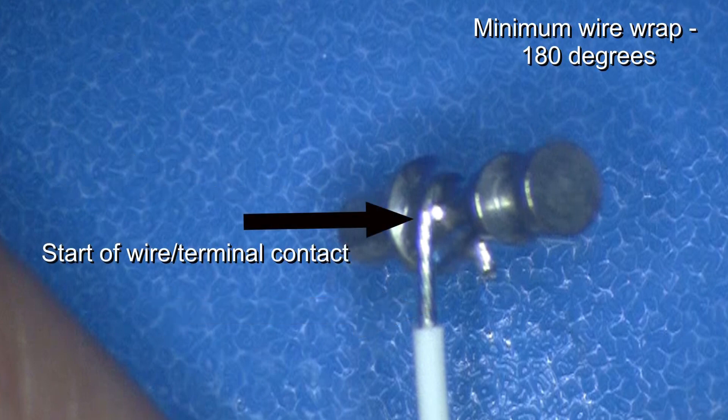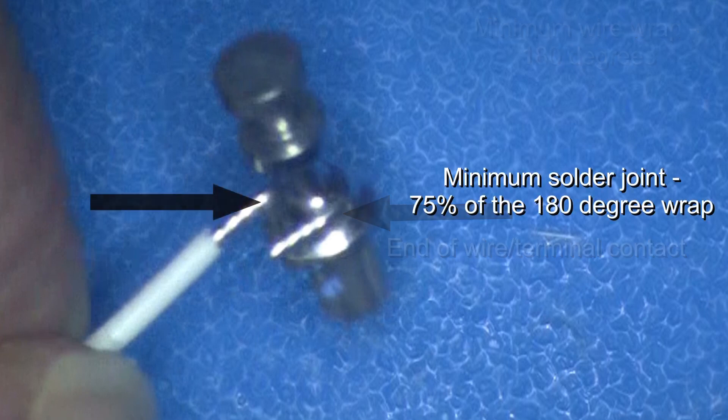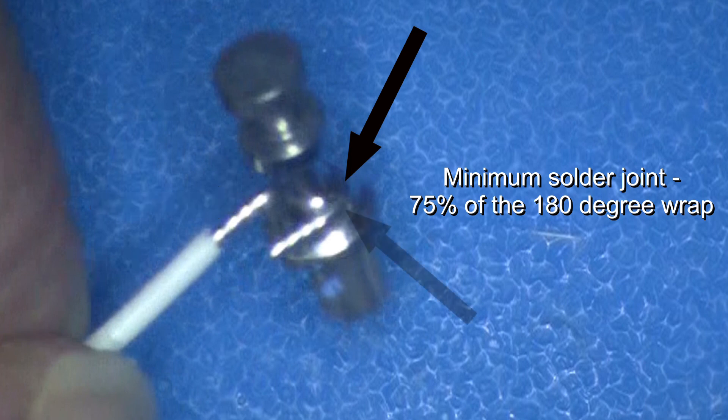The wire must wrap a minimum of 180 degrees around the terminal. 75% of that 180 degree wrap must be soldered to the terminal.